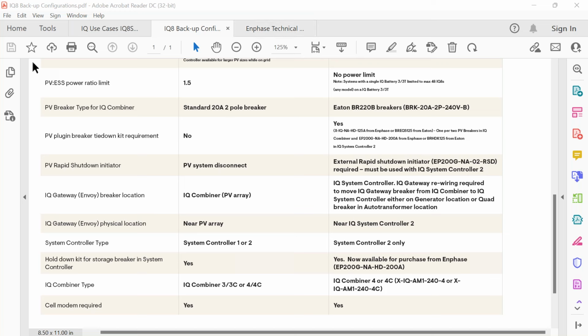If load controller 2 is compatible with IQ7 Plus and IQ8, what's the advantage of an IQ8 rather than using the previous generation of product? Well, the advantage really is the ability to have a sunlight only backup system without a battery. You can't do that with IQ7s. And the other advantage would be more flexibility in sizing PV with battery storage. So again, with the IQ7 series, there's a maximum ratio of 1.5 to 1 solar AC power to battery AC power. And with the IQ8, you can install a much larger PV system with a small battery.